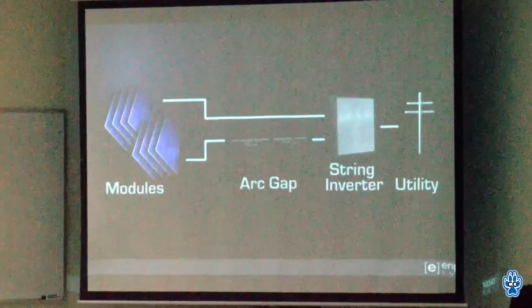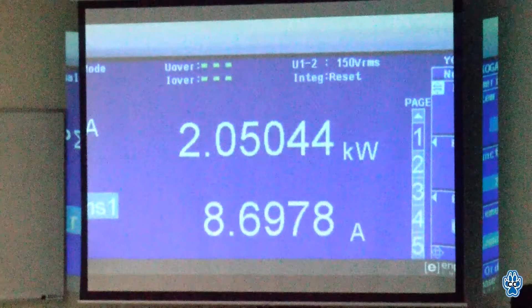The first case simulates a string inverter scenario. Remember, you've got 600 volts of DC there, kilowatts to the grid. As we establish an arc by simulating a wiring fault, the arc gets hotter and hotter. Temperatures can reach up to 4,200 degrees centigrade. This is hot enough to melt tungsten.